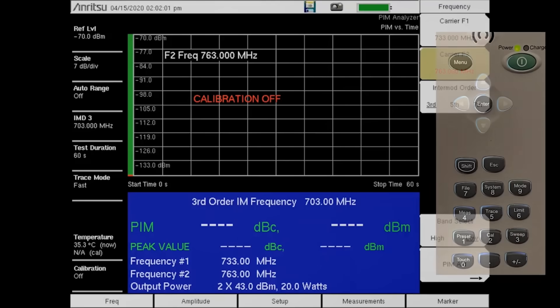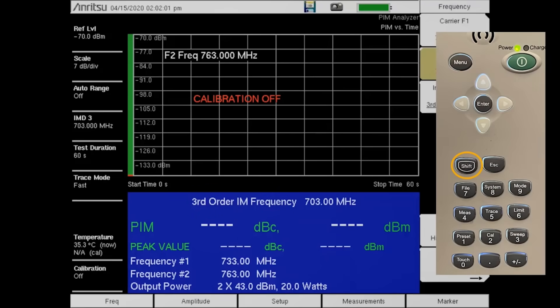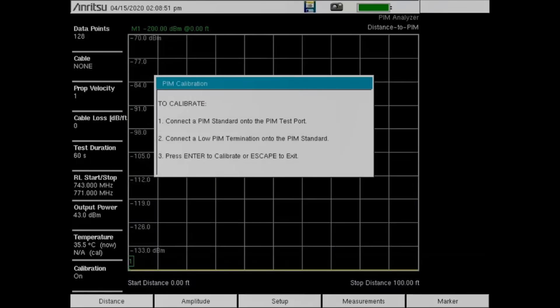Press the Shift key on the keypad followed by the Cal key to calibrate. Again, follow the on-screen instructions to complete the calibration and verify that calibration on is now displayed.